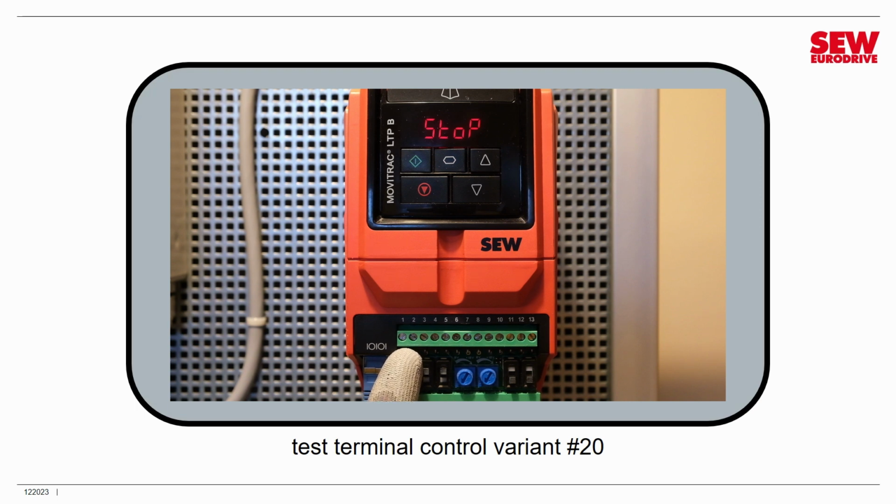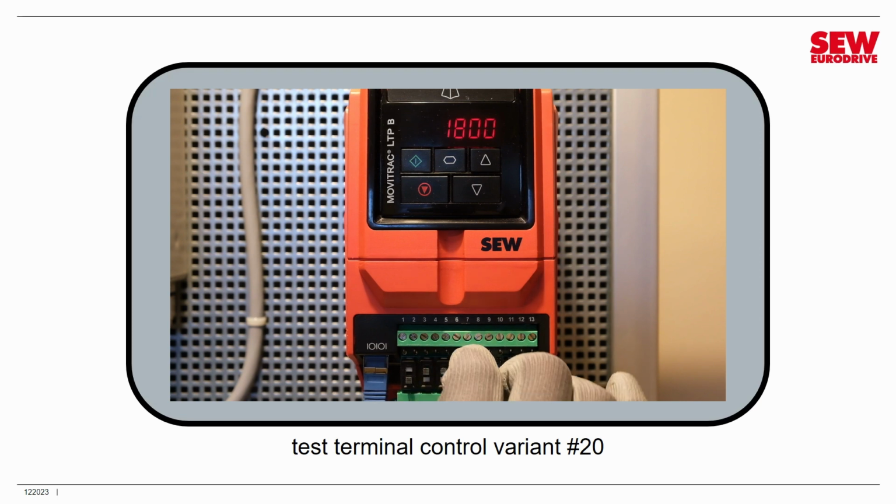The first thing I'm going to do is turn digital input 1 on. That will enable clockwise rotation. Notice we're not turning yet, but now I'm going to pulse the up button, which is digital input 3. I'll just flick it on and off quickly, and you can see, there we go. Our digital potentiometer is increasing our speed. If I leave the switch turned on, which is like holding down the button, it just goes all the way up to the maximum. All right, now we'll come down.